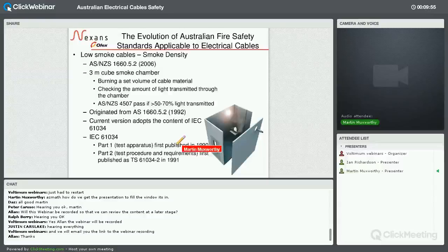To check the amount of smoke that cables give off, and in this particular case we are specifically talking about cable tests, there is another series of standards, AS1660 Part 5, Part 2, for example, which has a smoke density test. It's an interesting test in that a large 3 by 3 by 3 meter smoke chamber is used. Inside the chamber there's a sample of cable. A small tray of alcoholic mixture is used as a flame source, and essentially, as you'll see from a little image there, a light source is shined on one side of the chamber, and a light detector on the other side checks how much light it can receive from the light source.